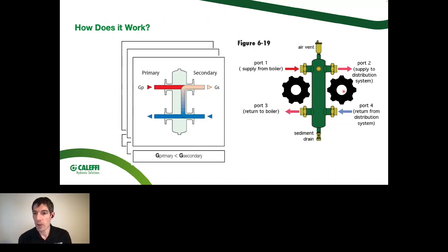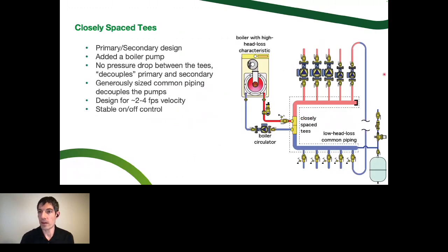Okay, let's talk about the first way to do primary secondary piping. Looking at the poll, we had answers for what's your go-to method before I get into the 3 different versions: a buffer tank, closely spaced tees, and hydro separators. We had 33% say buffer tank, 66% say hydro separators, and 0 say closely spaced tees. I think this is because we're doing this presentation in Canada. If we do this in the States, everybody's like, oh, you can save a lot of money with closely spaced tees. I would argue that's not necessarily the case, but I'll get into that in a few slides.